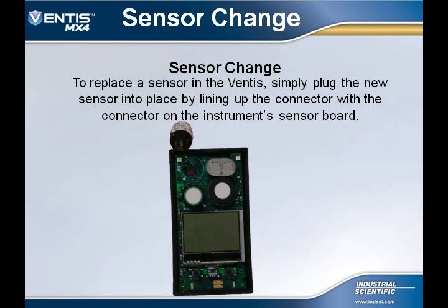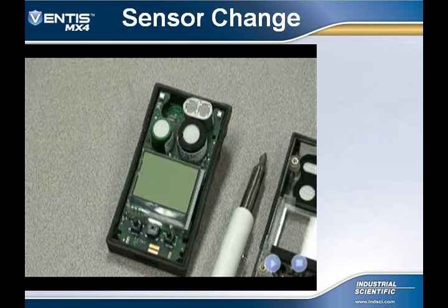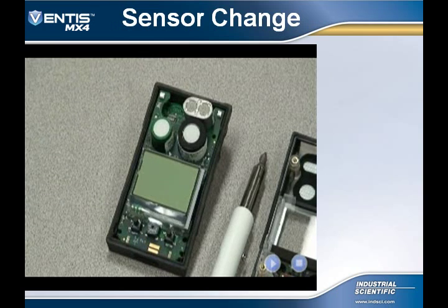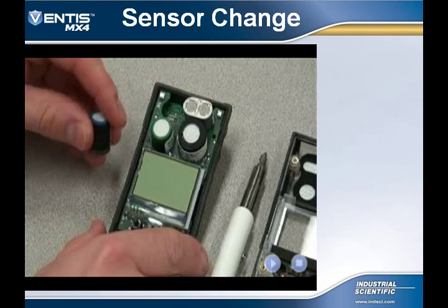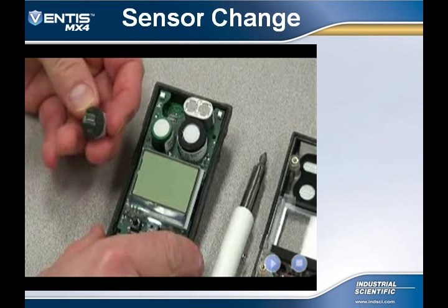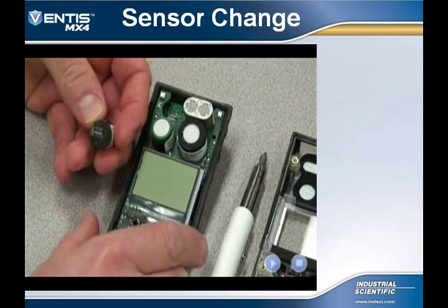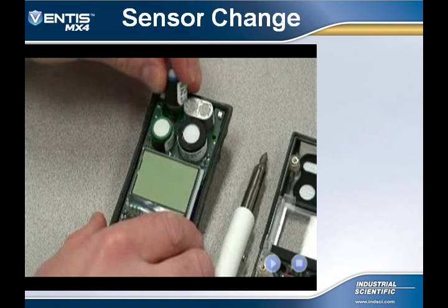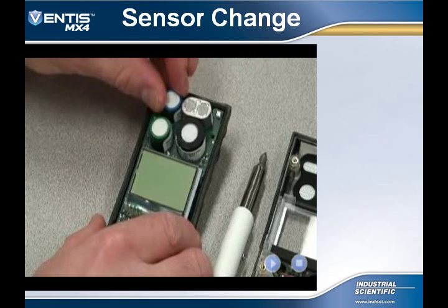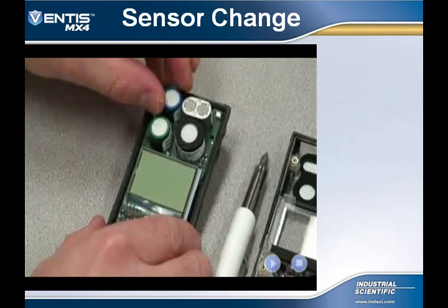To install a new sensor in the Ventis MX4, simply line up the sensor connector with the connector on the instrument's board and gently plug the sensor into the board connector. Here you will see a video on how to install a new sensor. To install a new sensor in the Ventis MX4, simply line up the sensor connector with the connector on the instrument's board. Then gently plug the sensor into the board connector.